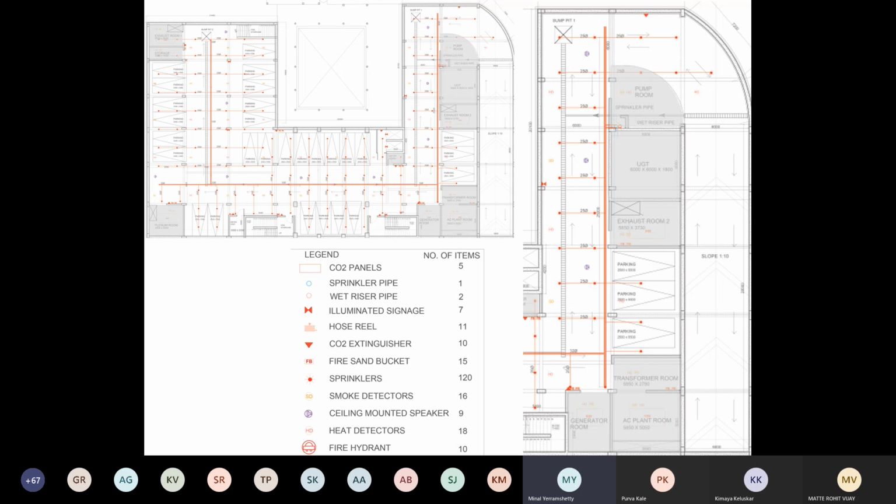Now that is my primary line. I can also do this, that the small thick line becomes my primary and then this becomes my secondary and then the last point can become tertiary. The choice is yours. You can do it this way or that way. Ideally I would like to go gradually down, because imagine a primary is like a 3-inch line, while your secondary is 1.5, but tertiary has to be half inch, no more no less. Or half inch or 3/4 inch, whatever.